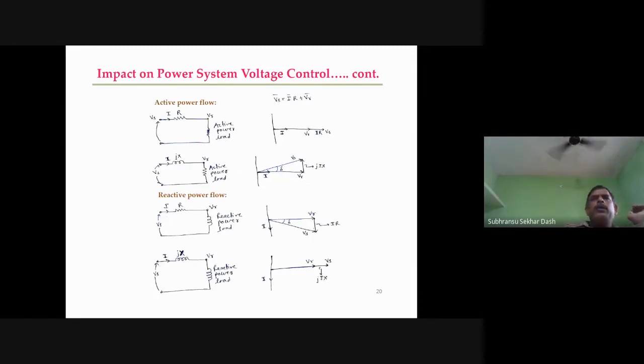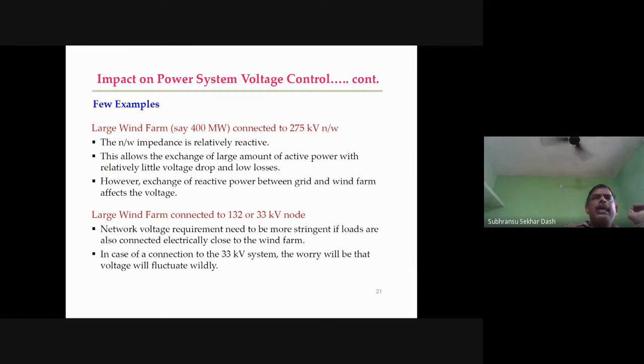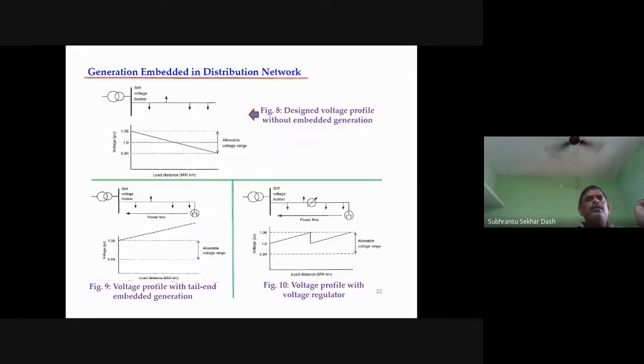Impact of wind power on voltage. A few examples: a large wind farm, say 400 megawatt, connected to a 275 kV network. The network impedance is relatively reactive. This allows the exchange of a large amount of active power with relatively little voltage change. However, exchange of reactive power between the grid and the wind farm affects the voltage. That is very, very important.